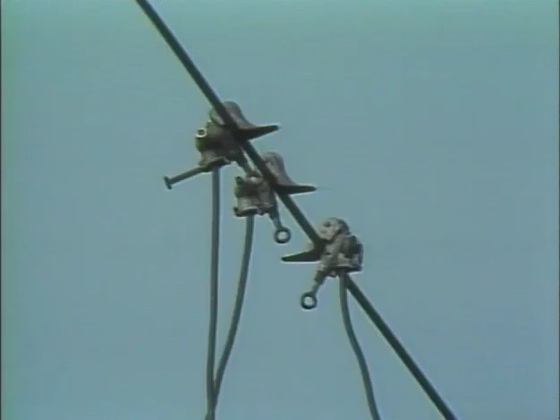A temporary ground is an electrical path between the work area and ground that's installed on a de-energized circuit for a short period of time. Temporary grounds are often used when maintenance or repair work is performed on a de-energized circuit. This type of ground will protect workers by keeping the work area at or near ground potential. Then, if the de-energized circuit should suddenly become energized, current flow is directed away from the work area to ground.